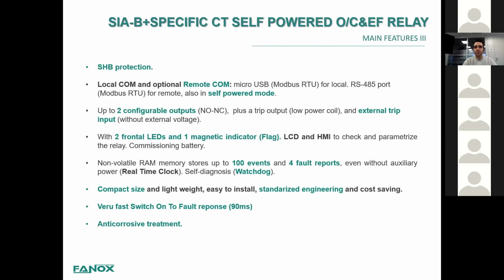We have a very fast switch-on-to-fault response, below 90 milliseconds. Just a small reminder: the switch-on-to-fault response means that when the relay is completely powered off, and then a fault occurs, the relay takes 90 milliseconds to wake up, detect the overcurrent, and trip the relay and the circuit breaker, sorry. This is also a very important parameter regarding self-powered relays.